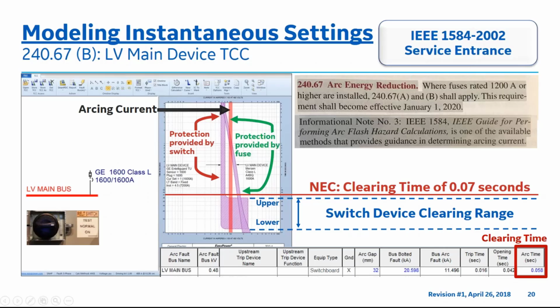Various arc flash software programs illustrate arcing currents differently, which in this case, a red vertical transparent arcing current line in the middle of the page has been manually added with the maintenance mode turned on. Different voltages across North America will change the position of the arcing current, moving it from the left to the right, as it is up to the qualified professionals to obtain the appropriate settings of the power distribution system applications. In a different slide, I will demonstrate an application that will model the routes, reduce energy let through, maintenance mode turned on for the 240.67B2 maintenance switch application. For now, let's move sequentially through the 2017 NEC code, where the application for B will be discussed next in a typical fused power distribution system.